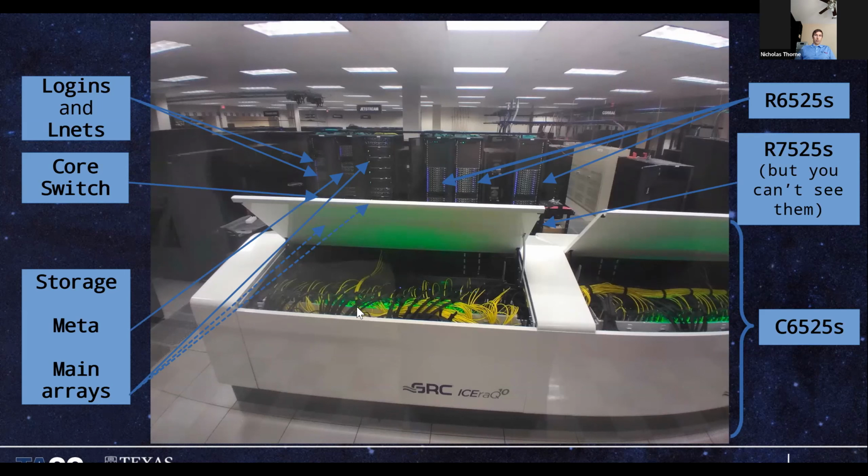But for us to go purely air cooled in this corner of the machine room would have been fairly challenging and probably more expensive than what we were hoping for, simply because the large air conditioning units that create the cold air cushion under the floor of the machine room are essentially about as far away from this corner of the machine room as they can possibly be.